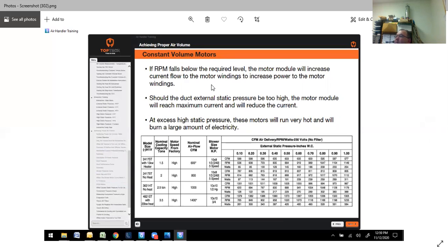If RPM falls below the required level, the module will increase power to the windings. Should the external pressure get too high, the motor module will reach maximum current and will reduce current. It will slow down. At high static pressures, these motors will run very hot, and they will burn a large amount of electricity. It could be the difference of 2.5 amps, 3 amps on operation. If it's a nice, smooth, low static situation, you could take that up to 9 amps.